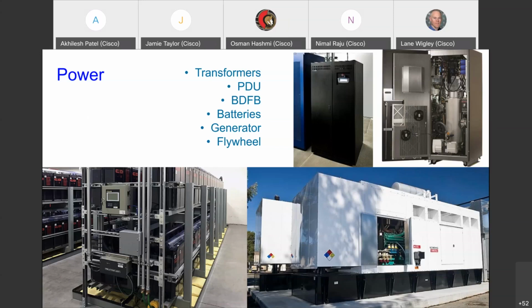They can be refueled if needed, but hopefully the power will come up before then. When you hear about feed redundancy in the hardware, or AB feeds, that's about having multiple power distribution paths inside the facility - for example, two different sets of banks, two different sets of battery distribution fuse bays, different things that control the power, clean the power, switch over between the batteries or what's coming in from the transmission lines. Having two different sets of that means if the A fails, we can go and work off of the B.